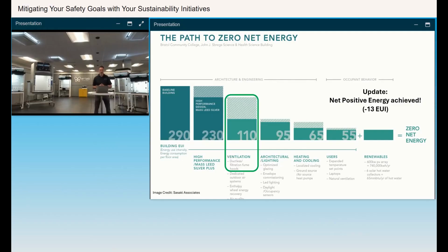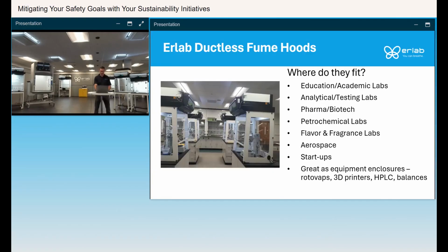The way they got down to zero net energy is they have a 3.2 megawatt solar array completely covering a parking lot on campus. That original high performance design with 18 ducted fume hoods was going to use up over half of the energy on that solar array. The zero net energy design with the ductless fume hoods allowed them to only use about 20% of that.